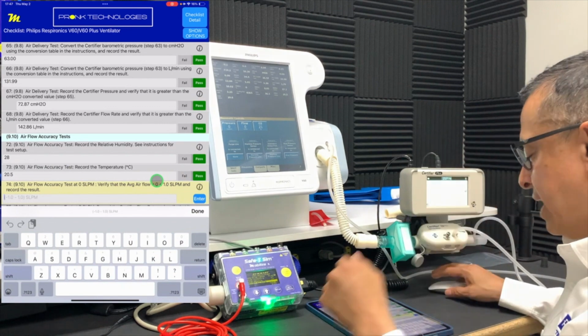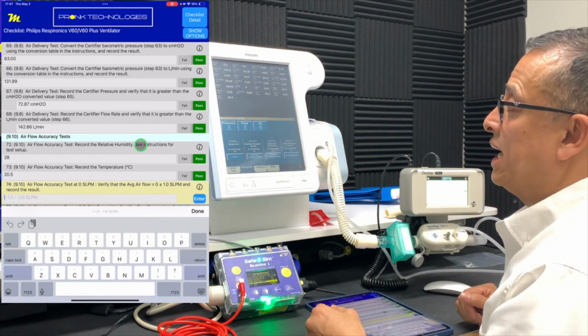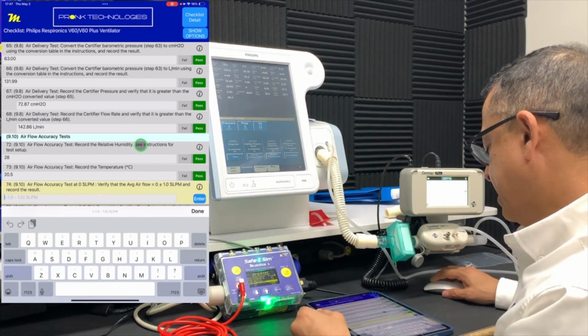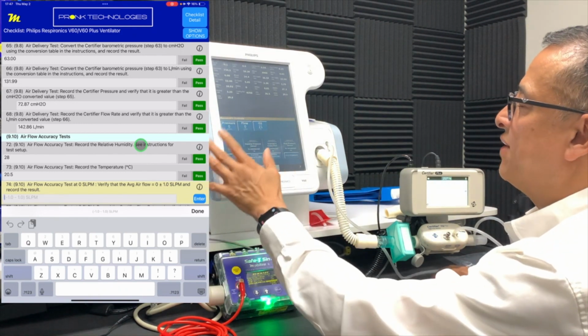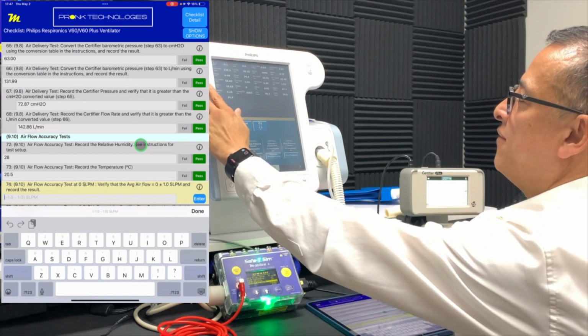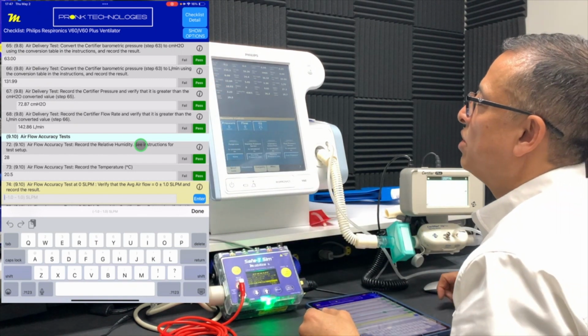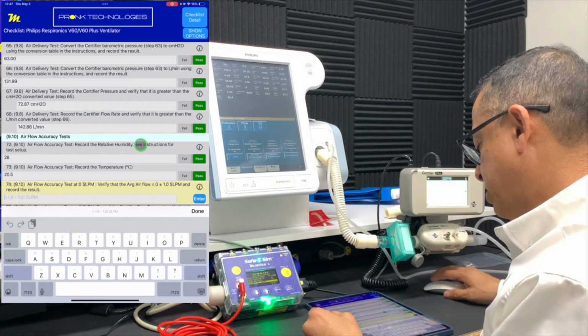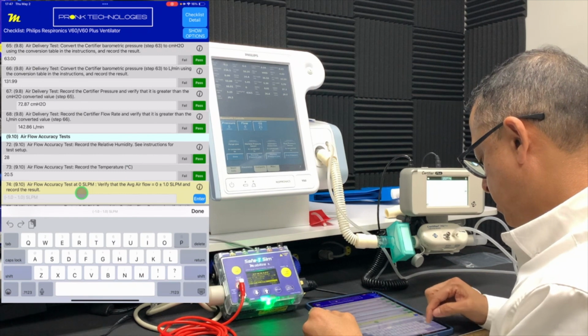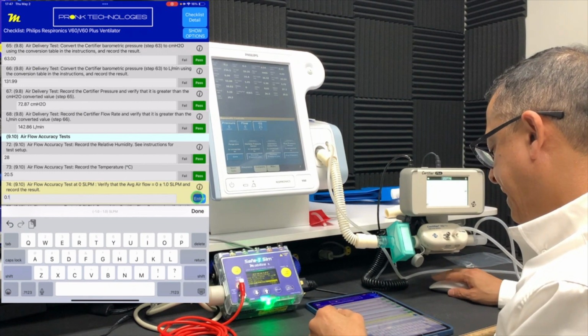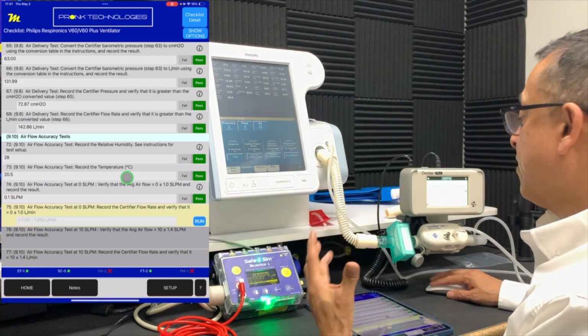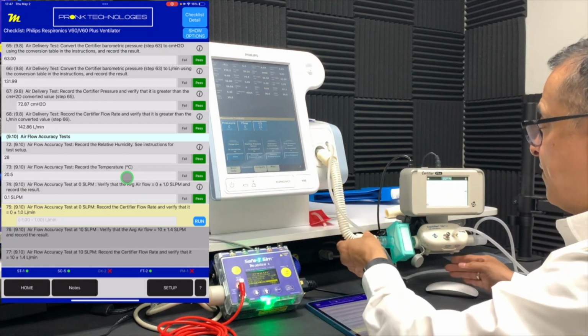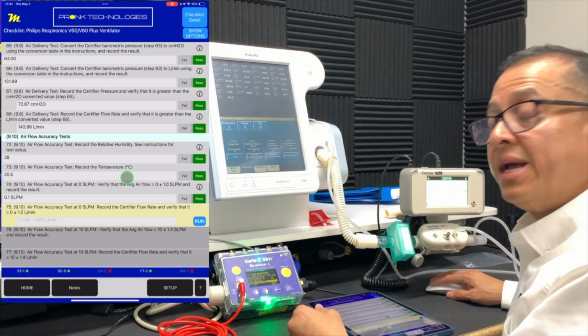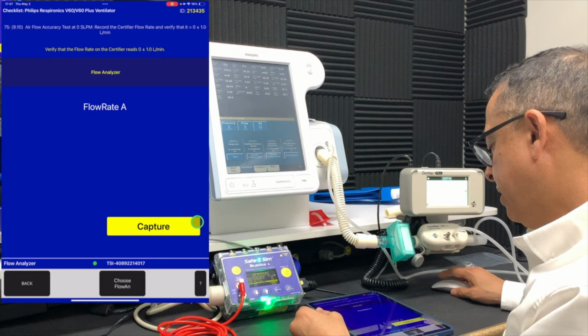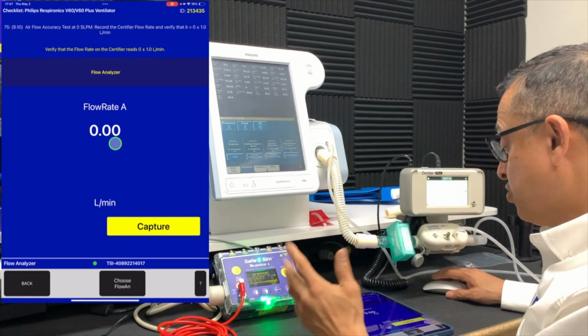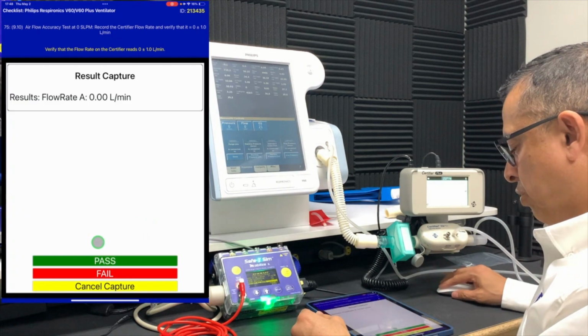So we want to do our first test at 0 and confirm that our flow is actually accurate on the ventilator when it's set to 0. We've got it set for 0, and I can see here that my value is actually at 0.1, so it's pretty much right at 0. So we'll capture that, and then what we want to do is confirm what the certifier is measuring. The question is, does the certifier measure that same value or within its tolerance as well? So we'll confirm here that the certifier is measuring 0 as well, which is what we want to see.